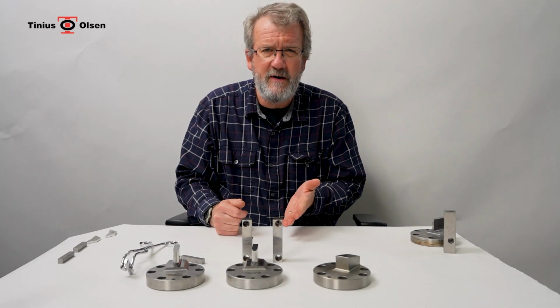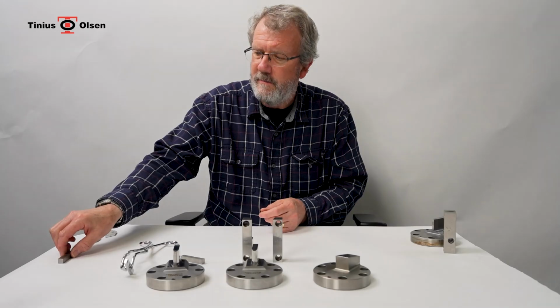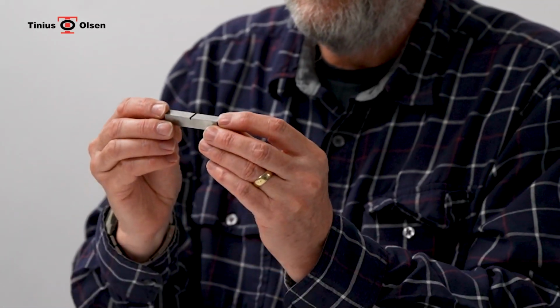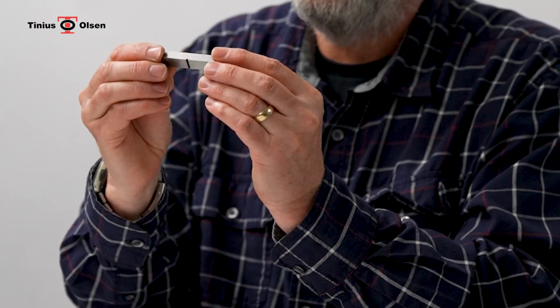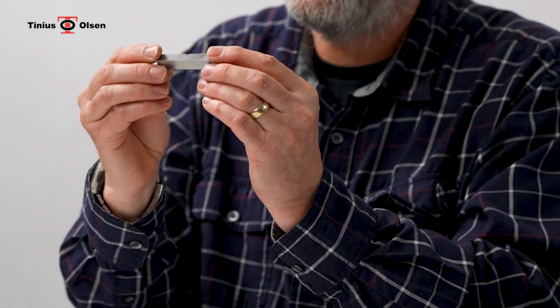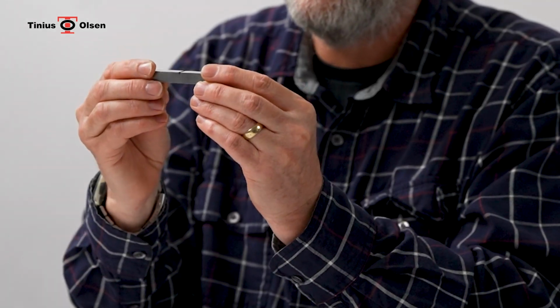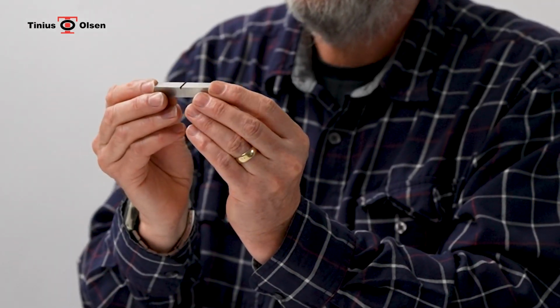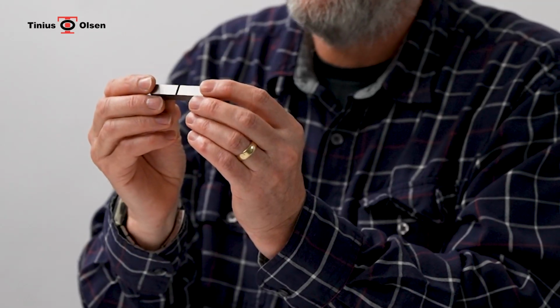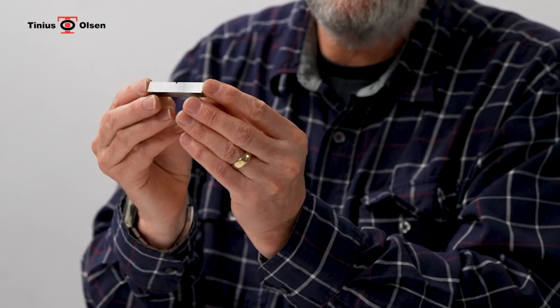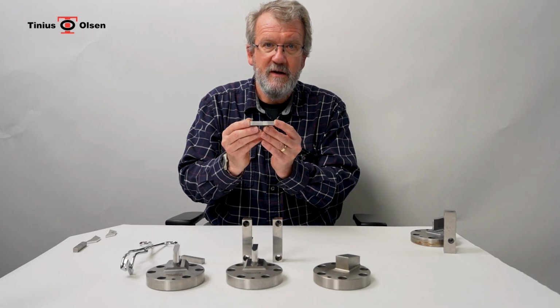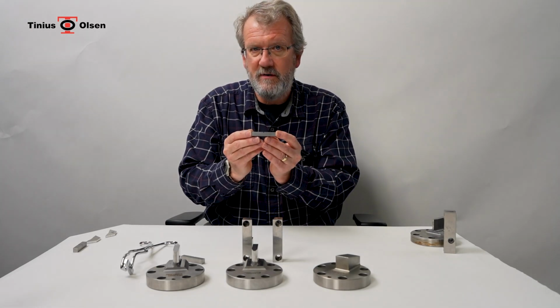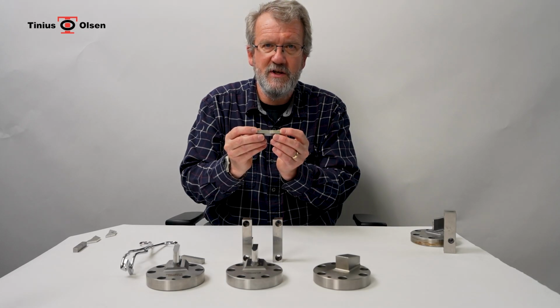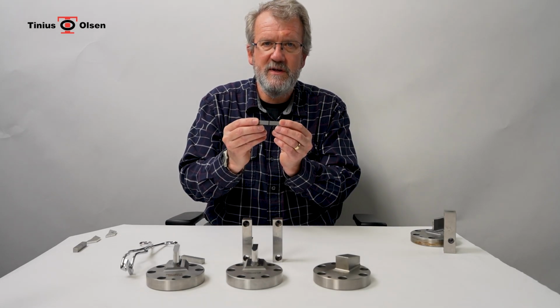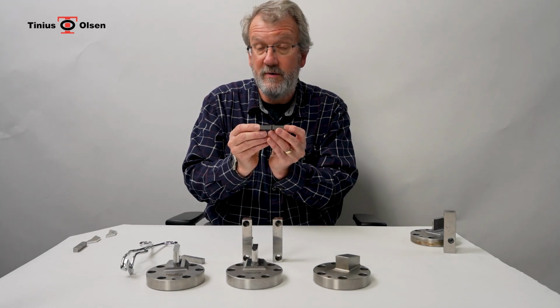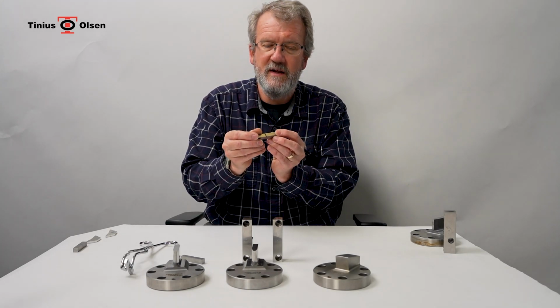These are typically a standard reference material that's very tightly controlled and manufactured to the highest specifications. A NIST specimen looks like this, and it comes with 3 batches of 5 samples. There's a low energy, a high energy, and a super high energy sample that allows you to test the actual energy outputs from the machine. These samples may need to be chilled to a specific temperature, checking the temperature of the bath, the operator use of the machine, and the machine itself. Those values are then sent to NIST, who then give you a thumbs up or a thumbs down on each range to say that it passes or fails.